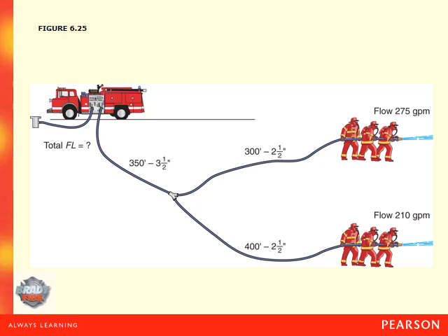And then our third line has a 3.5 inch supply line with a coefficient of 0.34. Now we're going to look at our total gallons per minute, and that's the total flowing from each line. So that's 485 gallons divided by 100, so our Q is now going to be 4.85. And then your length of hose is only going to be that of the supply line. So that's going to be 350 feet of that 3.5 inch. Again, divide that by 100 and gives you 3.5. So 4.85 squared times 3.5 times our coefficient of 0.34 equals 27.99 psi.